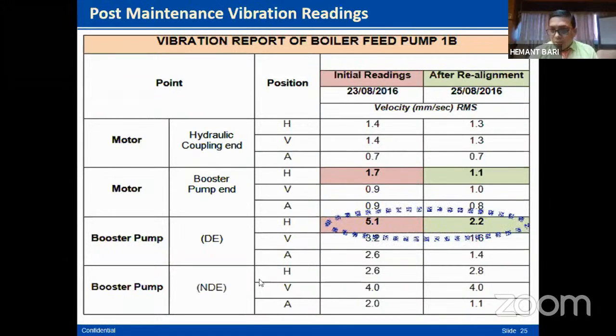See the result. The vibration reduced from 5.1 to 2.2, and 1.7 to 1.1.